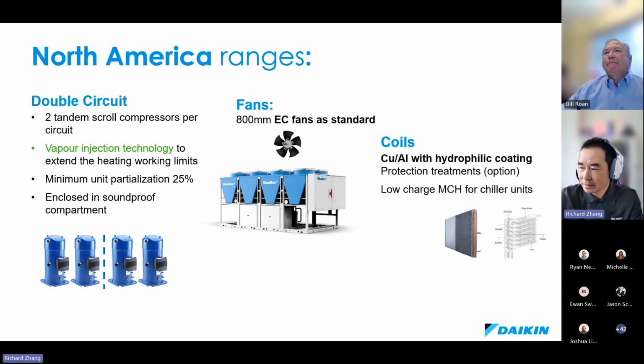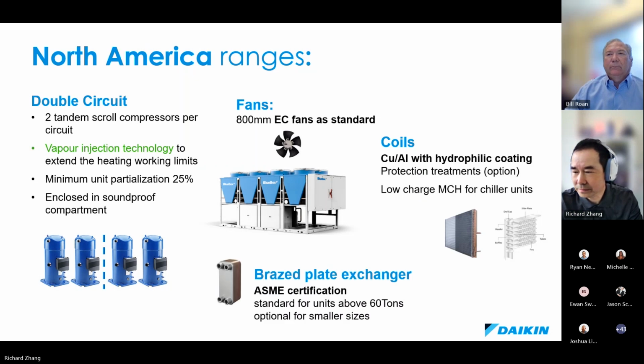On the other hand, let me give some introduction about the coil we're using. We use microchannel coil for the cooling-only chiller, but for the heat pump, reverse heat pump, or multi-purpose units, we make sure we're using a fin type of coil with hydrophilic coating, because defrost can be a huge topic here.